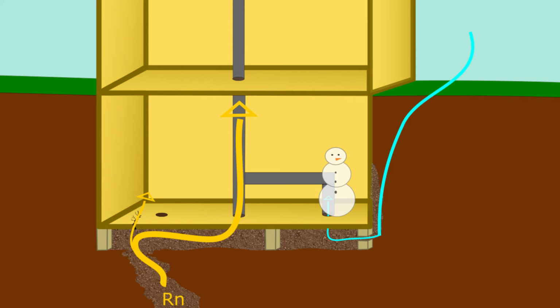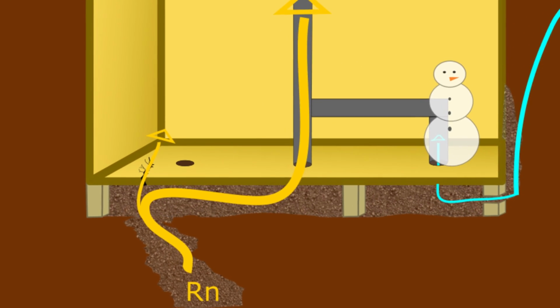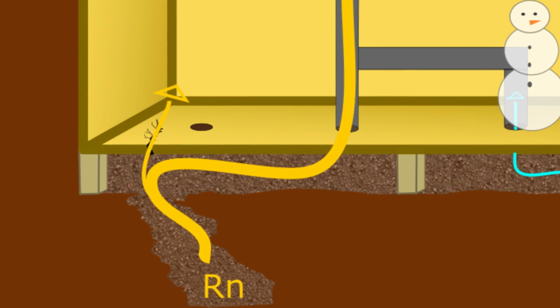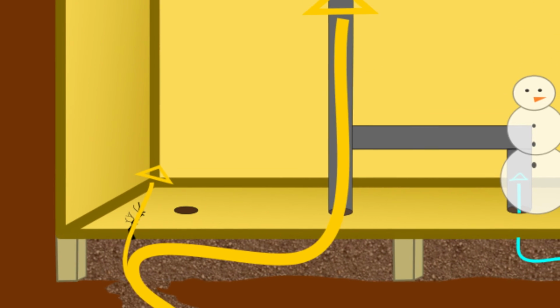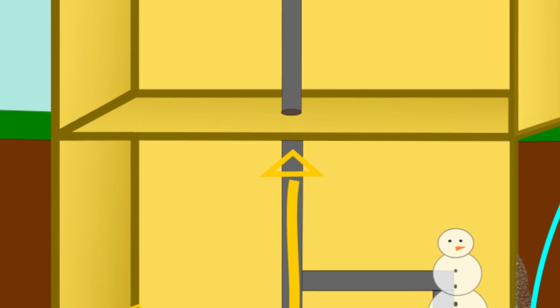Another consideration is that the mitigator may have depressurized the whole slab now, but what about 6 months from now when the water table is different? What about when the house's HRV intake is plugged, depressurizing the house? Maybe then the entire slab will no longer be depressurized with respect to the house. By sucking on the sub-slab, the mitigator could be bringing in more radon from below. So yes, the airflow through the crack is decreased, but there may have been an increased concentration of radon in that air.